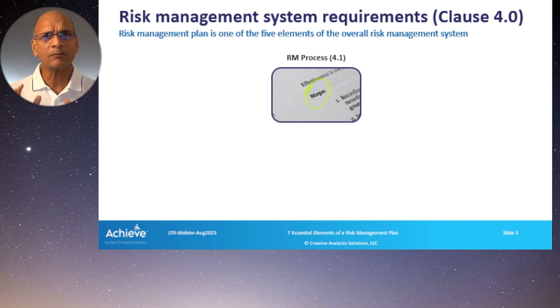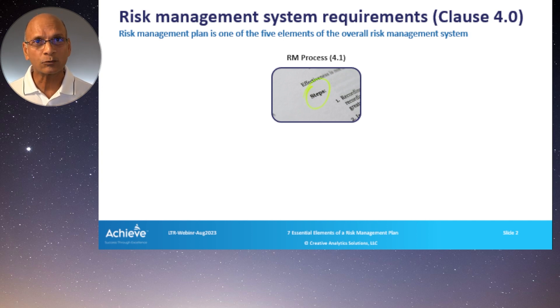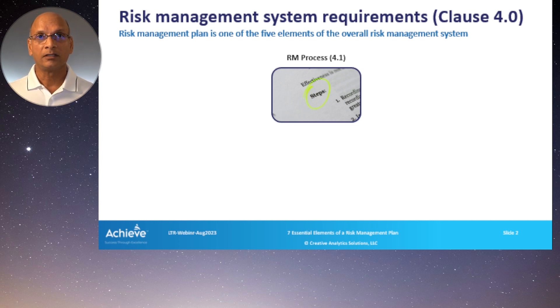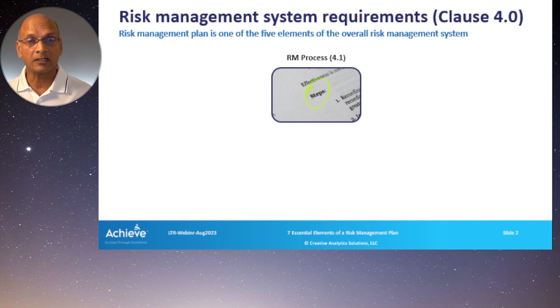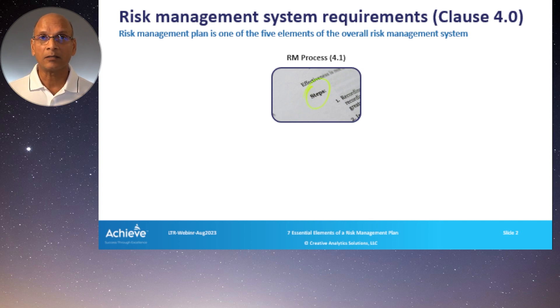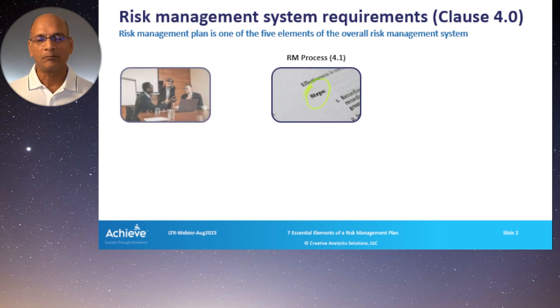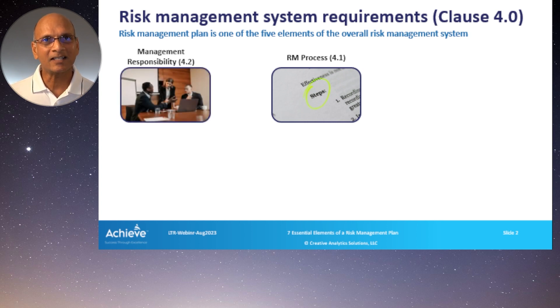In the middle of everything is our risk management process. That's what we do — we go through risk analysis, risk evaluation, risk controls, additional risk controls, final risk evaluation, and then we end up with a risk management report. But how does it all fit together?